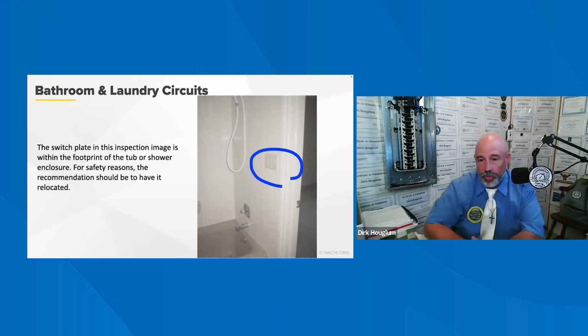I know we're running pretty short on time, but this was a common misconception that no switches could be within 3 feet of a bath or shower enclosure. This is correct for Canada, but it wasn't a requirement in the United States. But in 2023, section 406.9(C) of the electrical code does mention that the zone is changed from 3 feet horizontal and 8 feet vertical. So that would be considered a problem.